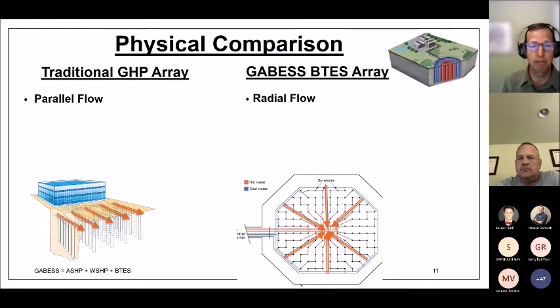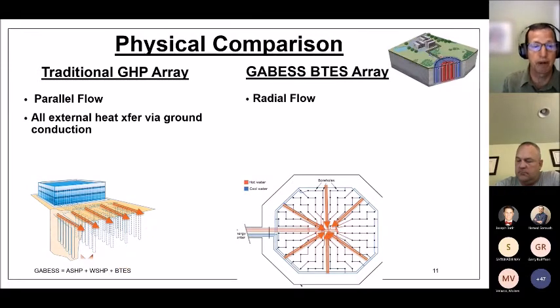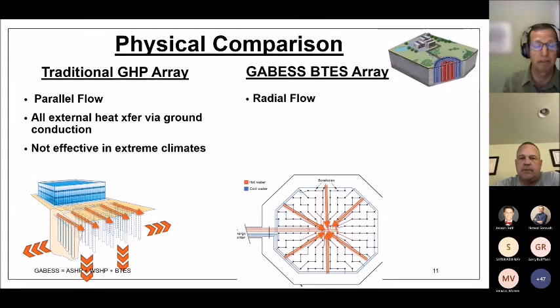So for a physical comparison, we've already looked at parallel flow versus radial flow. In a traditional geothermal heat pump array, our goal is to conduct heat away from the boreholes and into the ground beyond the borehole array using conduction. From the center of the field, that's quite a long way, and you have to cross other boreholes to get rid of the heat. So the center tends to heat up. As a result, it's not effective in extreme climates—there's just too much heat being transferred over too long a distance for too much of the year.